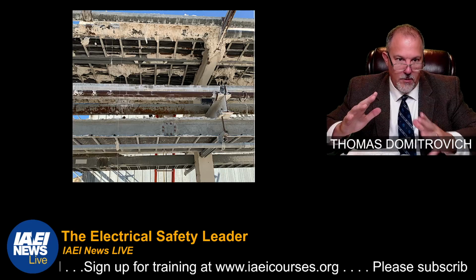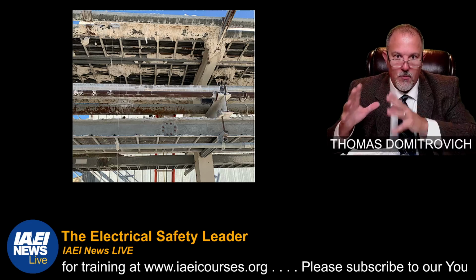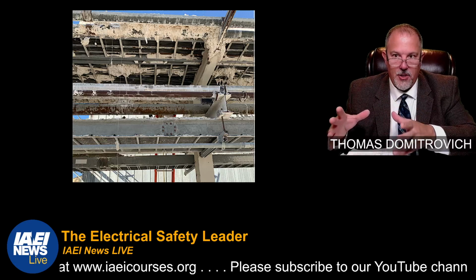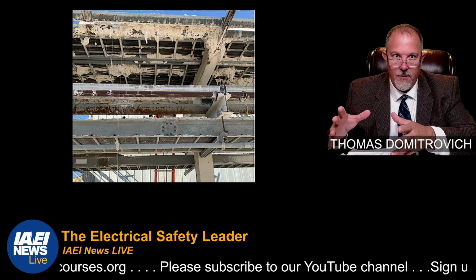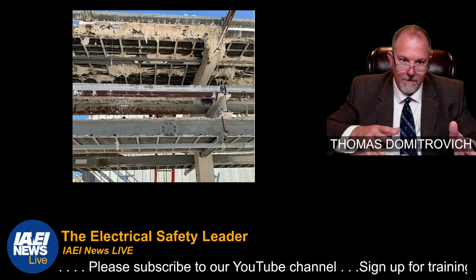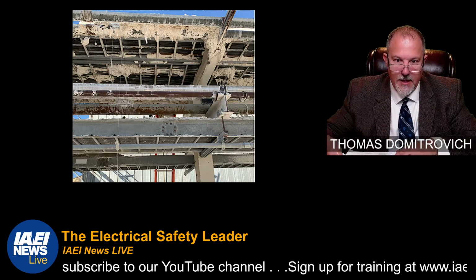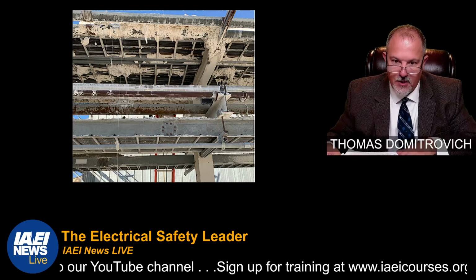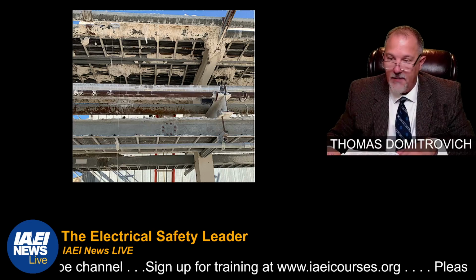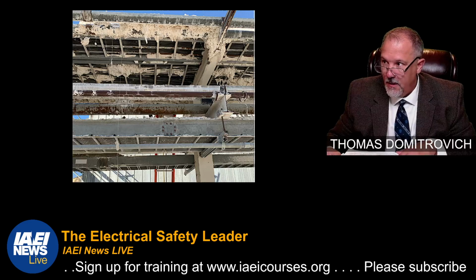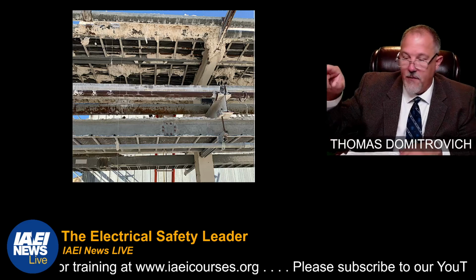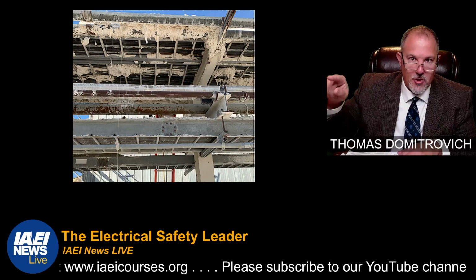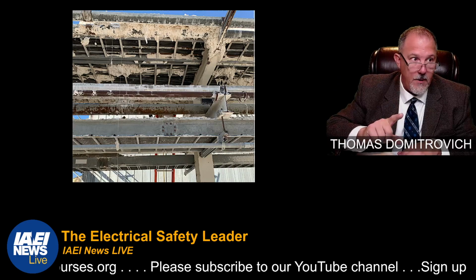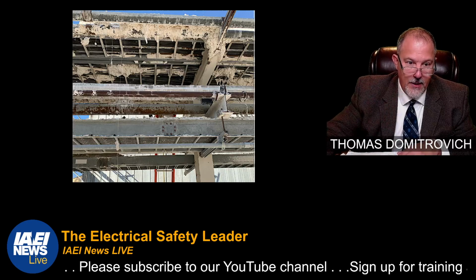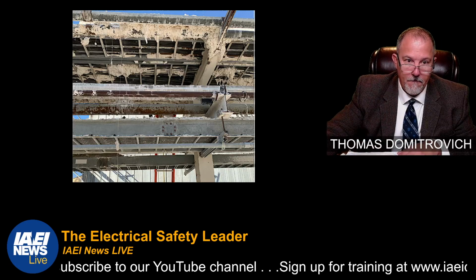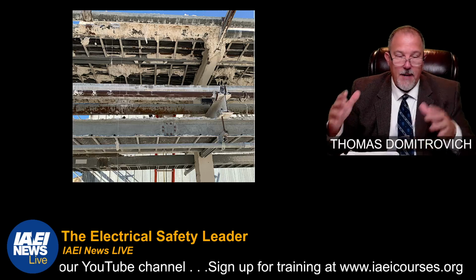Picking the right materials plays an important role in the application of your cable tray. So this is chemical corrosion and atmospheric corrosion. And this, I believe, is in a paper mill. That's not only not good for the cable tray, it's not good for your conductors either. So you've got to make sure you pick the right materials.